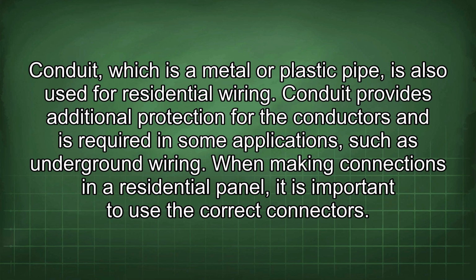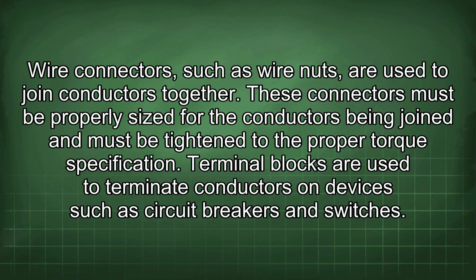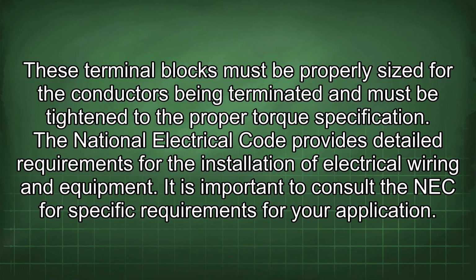When making connections in a residential panel, it is important to use the correct connectors. Wire connectors, such as wire nuts, are used to join conductors together. These connectors must be properly sized for the conductors being joined and must be tightened to the proper torque specification. Terminal blocks are used to terminate conductors on devices such as circuit breakers and switches. These terminal blocks must be properly sized for the conductors being terminated and must be tightened to the proper torque specification.